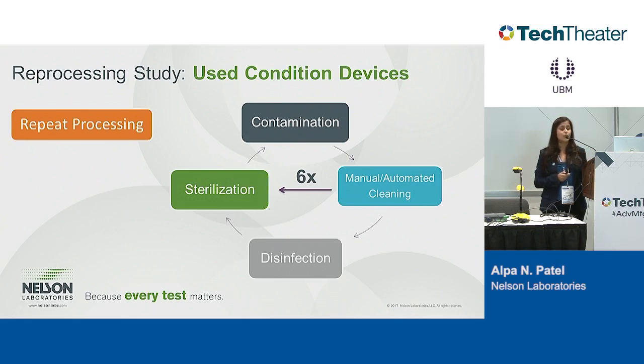If not, then we perform a test called simulated use cycle, where we're simulating the use of the life of a device and then test it at the end. Usually 6 cycles is what is recommended by the FDA. If you're going to ask me where the 6 comes from, we don't know. It's not written anywhere. It's a guidance that the FDA has given to manufacturers, and that's how we have come to know that 6 cycles is acceptable for these validations.